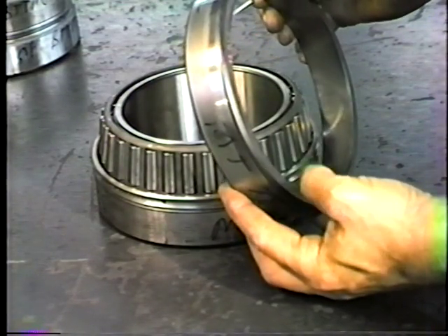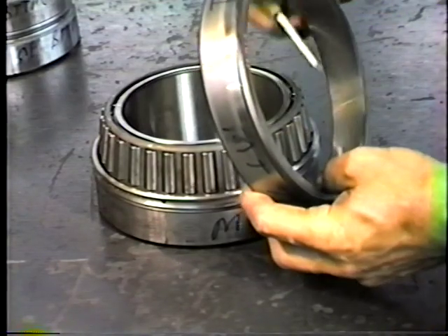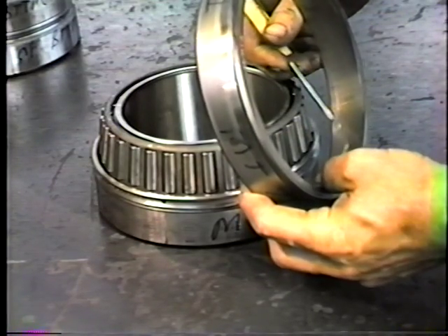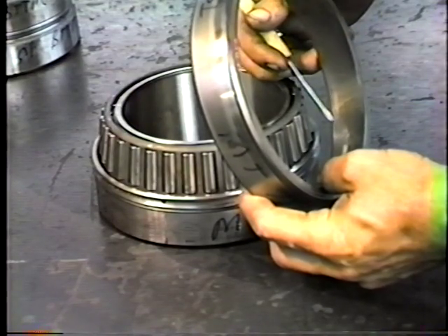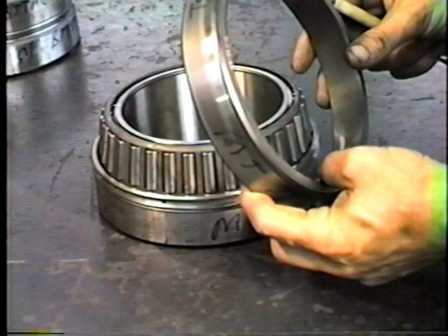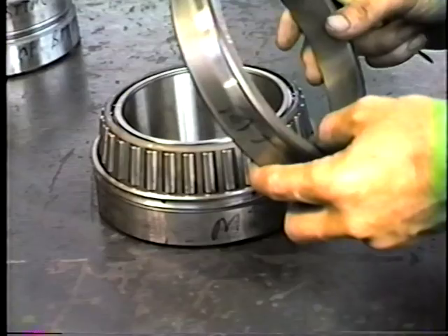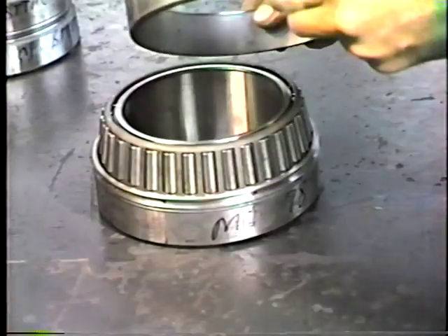Point to those two ridges on either side of the inside of that ring. Right there. That shows you there are some ridges in there from the wear. Well, that one is fairly well polished, and there's no apparent brinelling in there at all, is there? No. Okay. What we ought to do now that we've got the lights on is bring that other one back over here again, too.